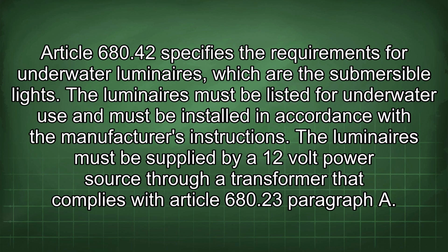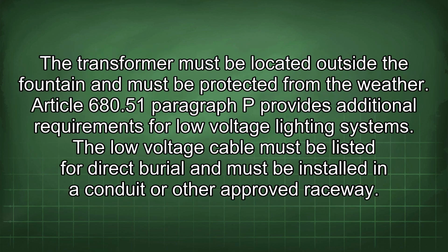The luminaires must be listed for underwater use and must be installed in accordance with the manufacturer's instructions. The luminaires must be supplied by a 12-volt power source through a transformer that complies with Article 680.23 paragraph A. The transformer must be located outside the fountain and must be protected from the weather.